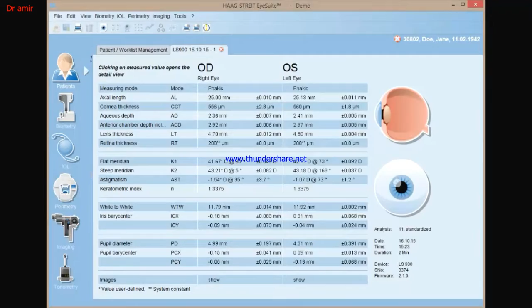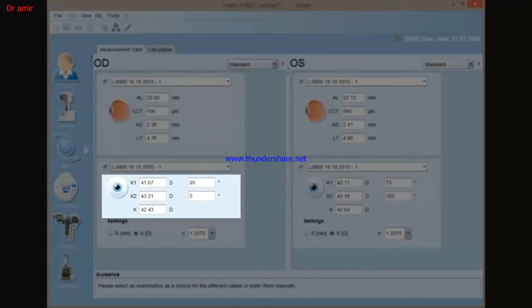Measurement data can be excluded entirely by unchecking the box to the right of the measurement. The K1, K2, Axis 1 and Axis 2 measurements may also be excluded individually with a right click of the mouse. Excluded measurements will remain in the database and are not permanently deleted. Adjusted results will be displayed with an asterisk on both the keratometry screen as well as on the results overview page. Right and left eye measurements will open independently. Keratometry measurements acquired from secondary sources can also be manually entered in the EyeSuite IOL calculation section.